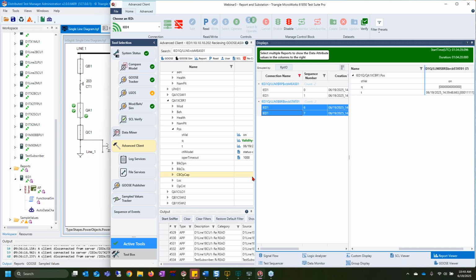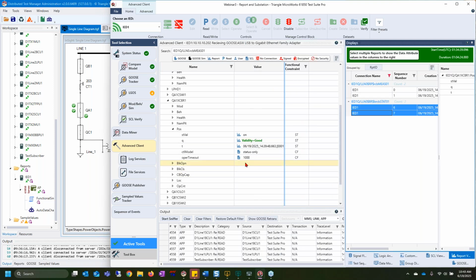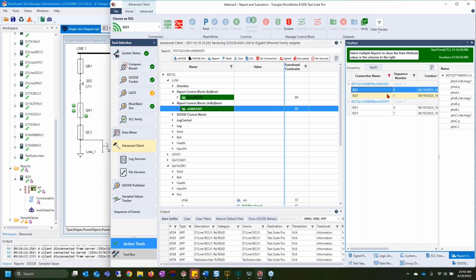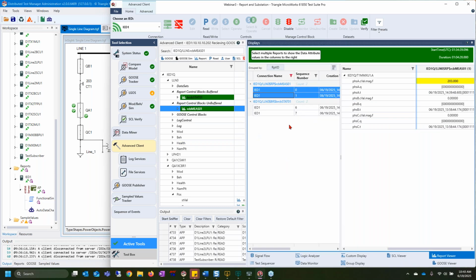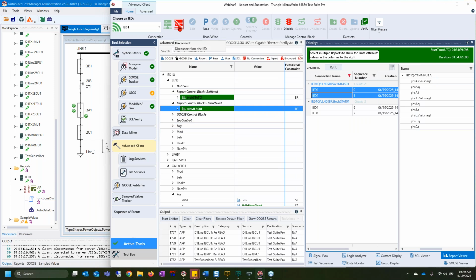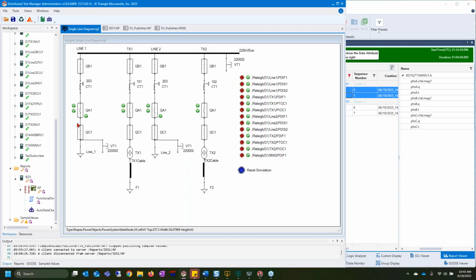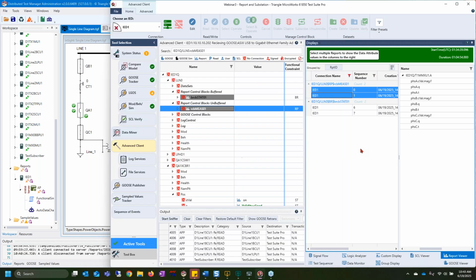date. Now, let's talk about buffered versus unbuffered. We're also seeing some analog values coming across, and you can see it jumping back and forth between 0, the breaker's open, there's no current, and 203, the breaker is closed, the current has resumed. If I was to say disconnect from this device due to a network error, or we had to restart the system or something, we'll see all of this go offline. We're no longer connected.